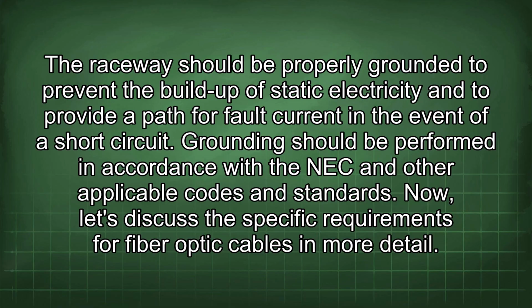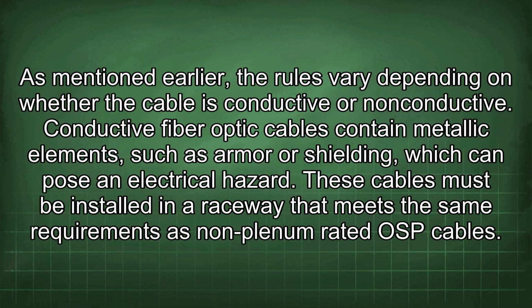Now let's discuss the specific requirements for fiber optic cables in more detail. As mentioned earlier, the rules vary depending on whether the cable is conductive or non-conductive. Conductive fiber optic cables contain metallic elements such as armor or shielding, which can pose an electrical hazard. These cables must be installed in a raceway that meets the same requirements as non-plenum rated OSP cables.